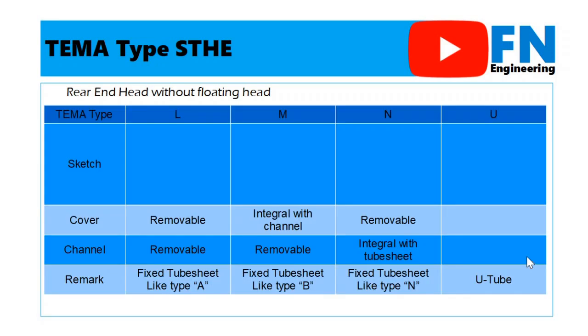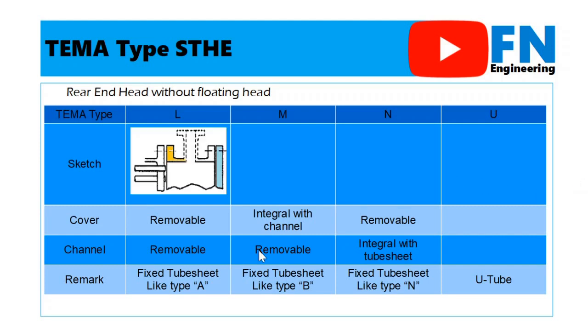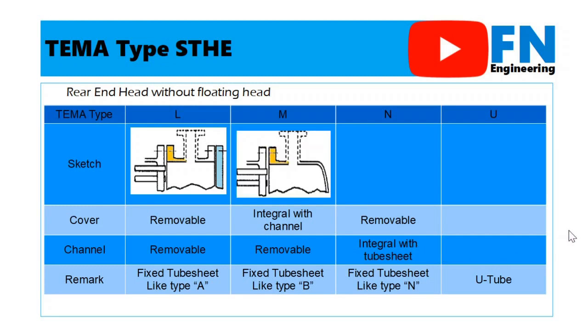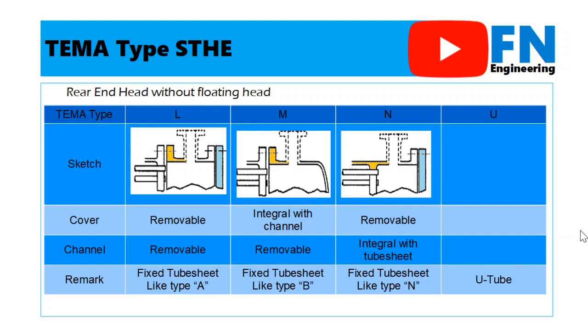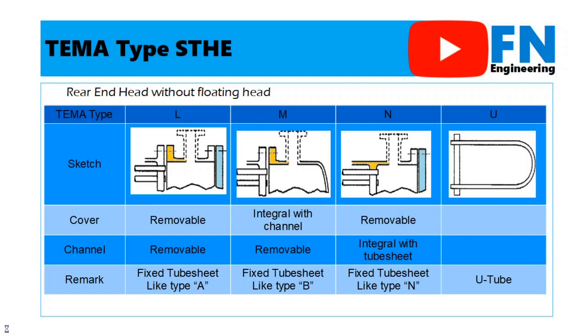The last configuration is the rear head arrangement. In this material, we divide the type of head into two sub-arrangements, namely rear head with floating head or floating tubesheet, and without floating head or fixed tubesheet. First, we are going to explain the rear head without the floating head. There are four configurations: type L, type M, type N, and type U. Type L is like type A, type M is like type B, and type N is like type N in the front head. Meanwhile, type U is for shell and tube heat exchanger using U-tube.